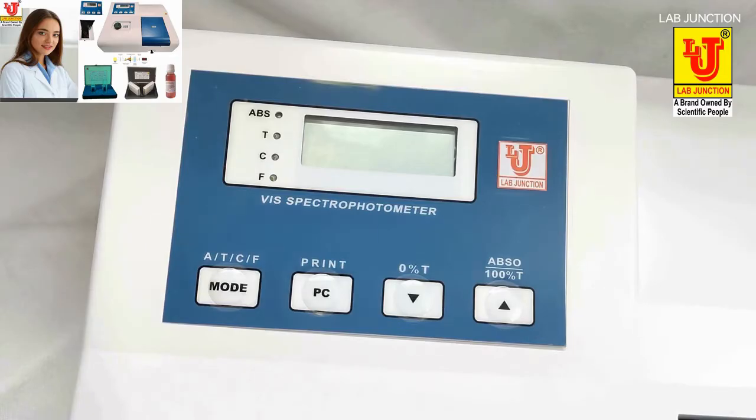In the spectrophotometer, a prism or grating is used to split the incident beam into different wavelengths. By suitable mechanisms, waves of specific wavelengths can be manipulated to fall on the test solution. The range of the wavelength of the incident light can be as low as 1 to 2 nm. The spectrophotometer is useful for measuring the absorption spectrum of a compound, that is, the absorption of light by a solution at each wavelength.